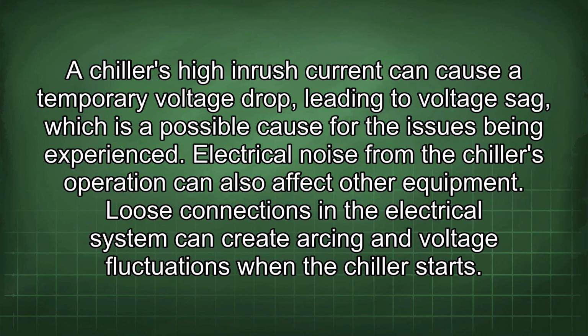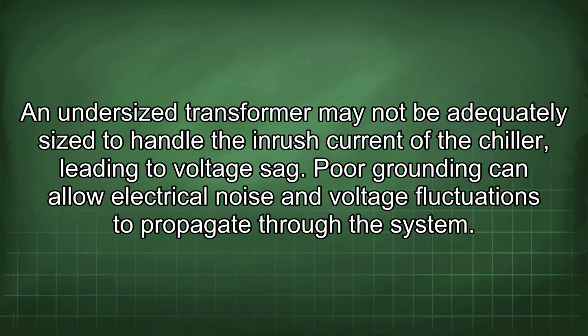A chiller's high inrush current can cause a temporary voltage drop, leading to voltage sag, which is a possible cause for the issues being experienced. Electrical noise from the chiller's operation can also affect other equipment. Loose connections in the electrical system can create arcing and voltage fluctuations when the chiller starts. An undersized transformer may not be adequately sized to handle the inrush current of the chiller, leading to voltage sag. Poor grounding can allow electrical noise and voltage fluctuations to propagate through the system.